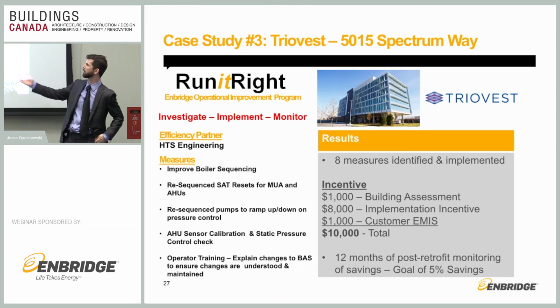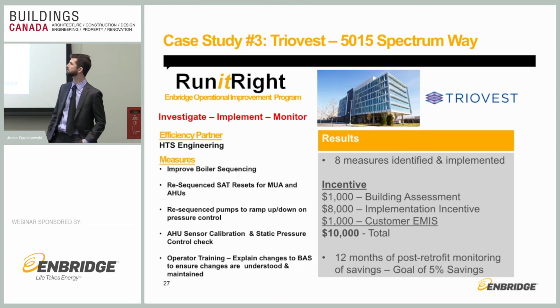They went in and audited and found that they could improve the boiler sequencing. They resequenced supply air temperature resets for the makeup air and the air handling units. They resequenced pumps to ramp up and ramp down on pressure control. They were drifting a little bit, so there was opportunity there.